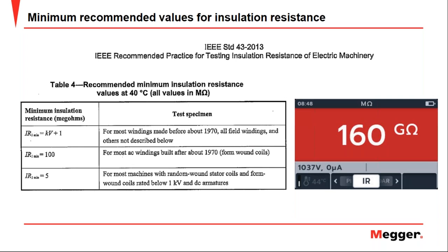If the motor or the winding is built after 1970, the minimum insulation resistance value is 100. For most machines with random wound coils or rated below 1 kV, the minimum insulation resistance value is 5. But once again, if the OEM tells you what the minimum insulation resistance value should be, and it is not the same or not even close to those seen in this table, you have to take into account what is indicated by the manufacturer.